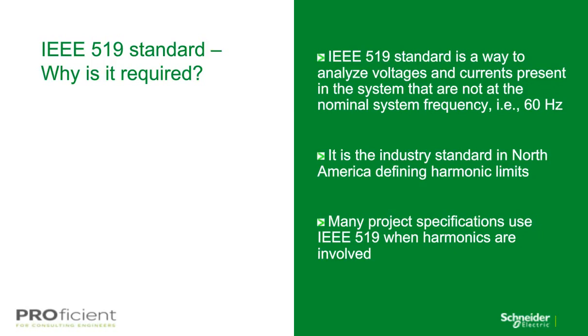The typical error lies in specifying the PCC and objective levels of THDV or TDD. The specific methods of calculation typically vary widely, part of the reason why the standard was originally set up in 1992. And it is required to verify that compliance has been designed into the equipment, provided harmonic analysis is the only method that can verify true compliance. However, each vendor will typically be held responsible for their respective equipment, where the compliance lies at the system level for IEEE 519.